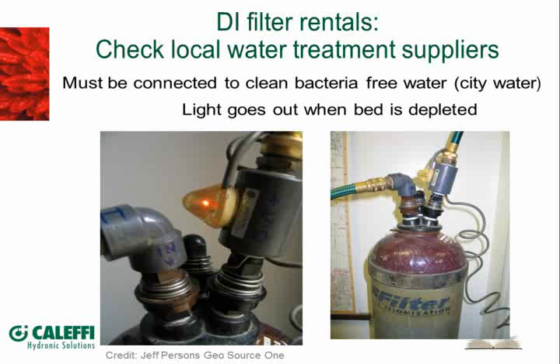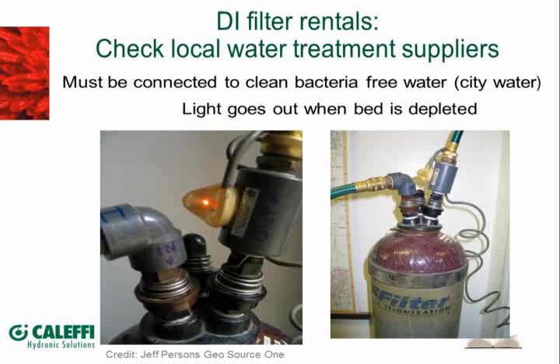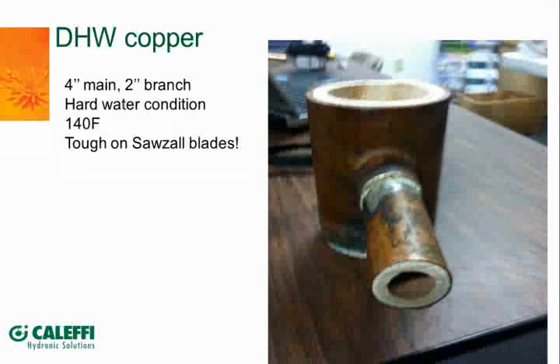On commercial jobs you may have as many as 4 of these columns all ganged up and run together and then feed them from city water to flush a commercial system. But the expense of doing this is far less than the expense of trying to maintain a system that's having problems with scaling and corrosion because you didn't take the necessary precautions. Yeah, so you would just get a chemical regimen that's trying to correct the problem of the bad water that's in there, so you're just adding an inhibitor chemical every couple of months when in fact you should just be changing the water out and putting in better quality water.